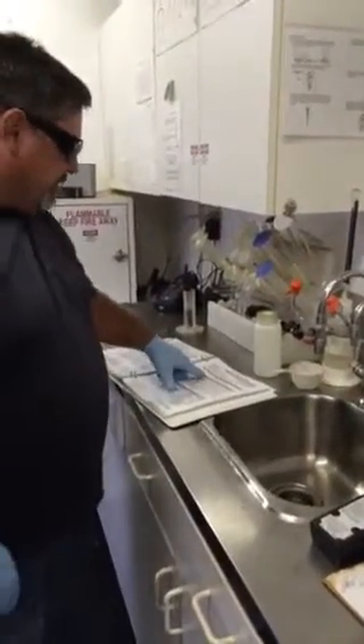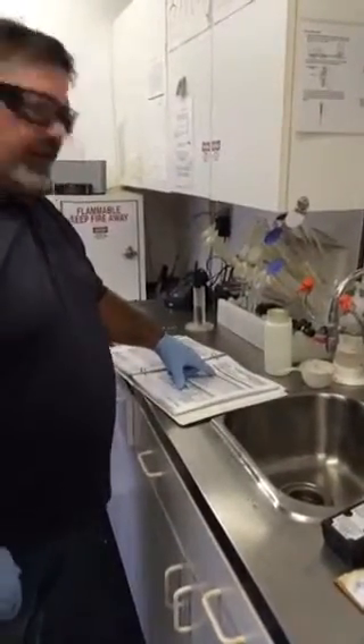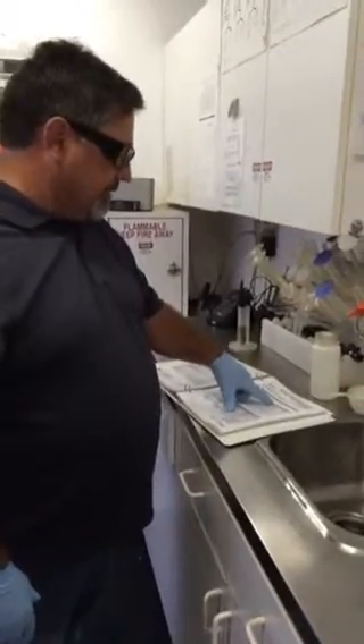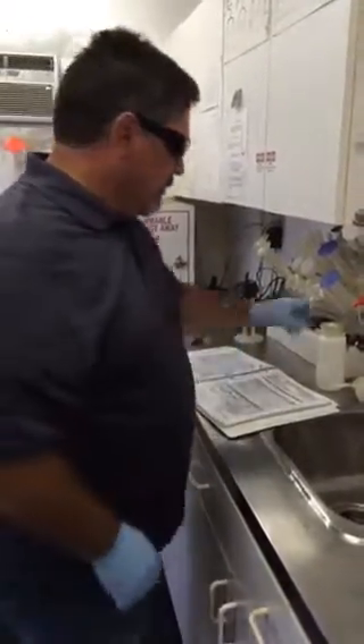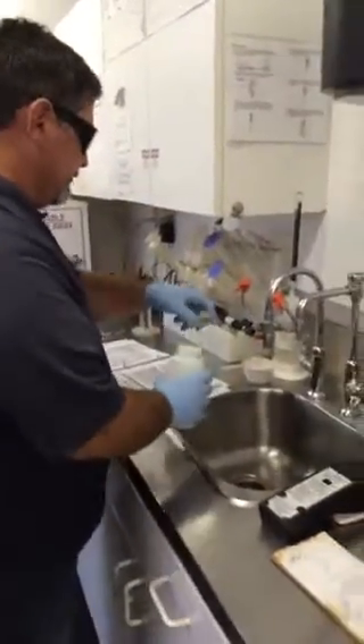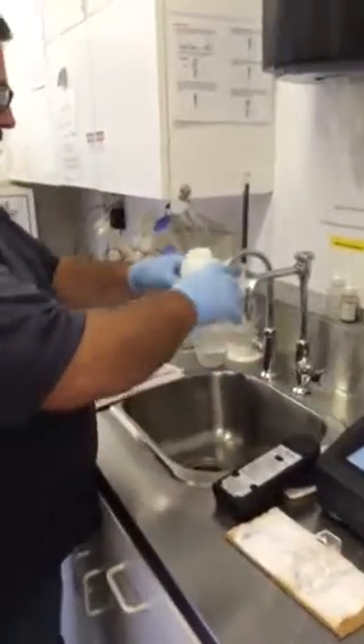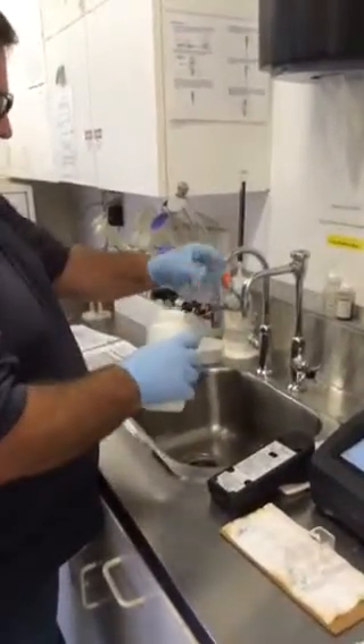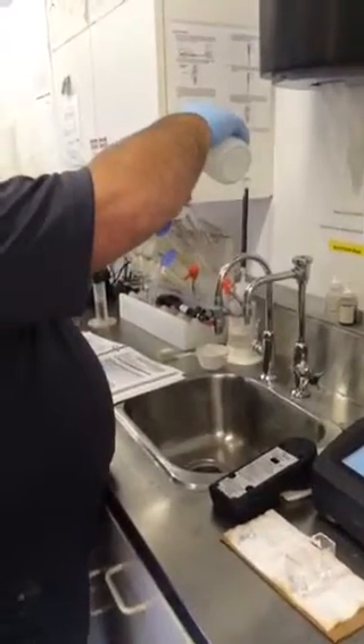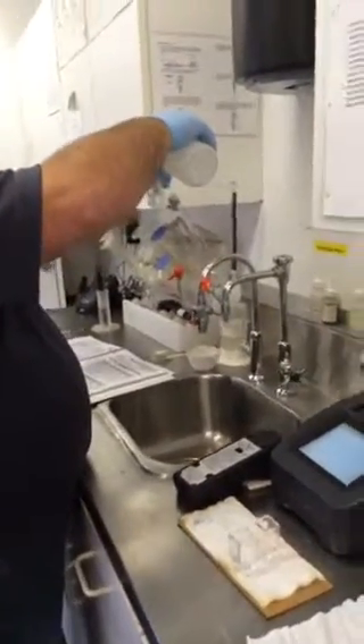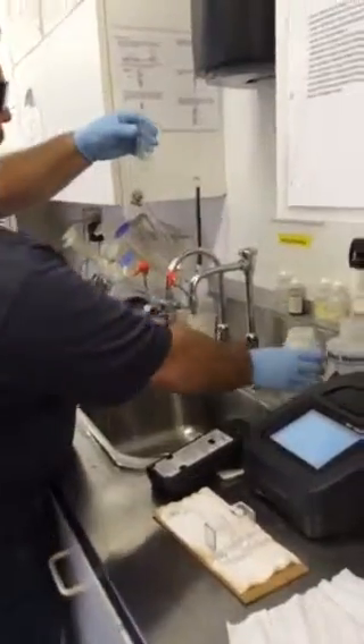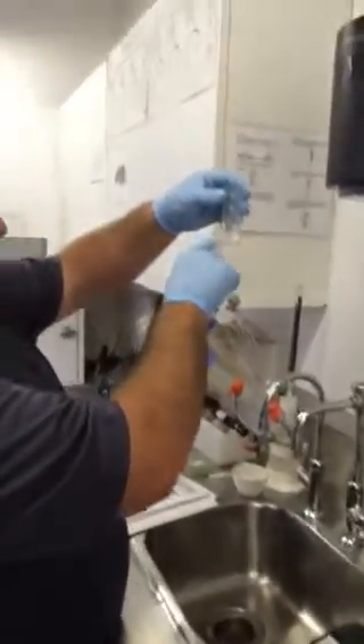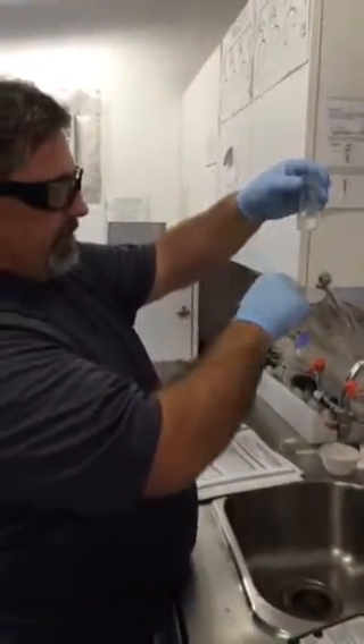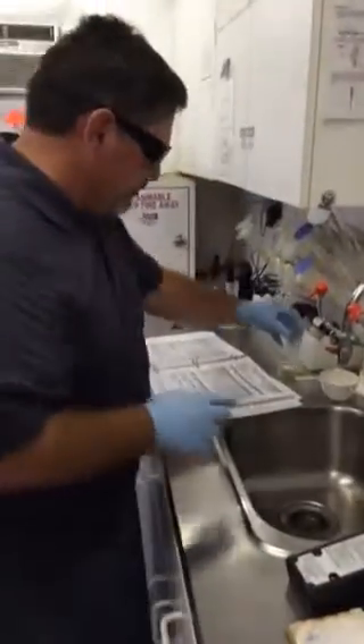So on the test, it starts off here with 10 mLs of sample and 90 mLs of DI. So what we're going to do is take our sample here. We're going to get 10 mLs of that sample, so we're going to clean that up a little bit. We're going to put 10 mLs of our cooling water sample in here. You want to get it to where the bottom of the meniscus is right at the 10 ml mark. So we know we're good there.